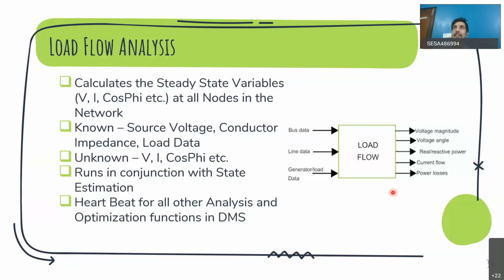This is needed because, to perform any optimization or correction on the network, the whole network scenario has to be known. You get data from the substation and from RMUs, but if you don't have RMUs, like along a conductor, you don't know how much current is flowing since there's no SCADA there. So at any point without SCADA, load flow calculates the values so you have the complete network picture in front of you, matching what's actually in the field, so you can optimize accordingly. Known values are used as input, and load flow calculates the unknown values.